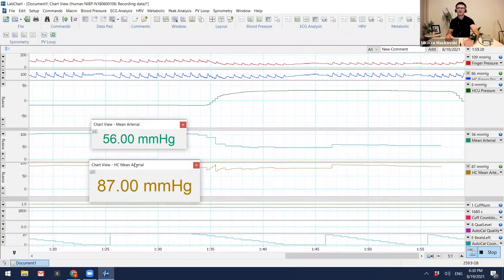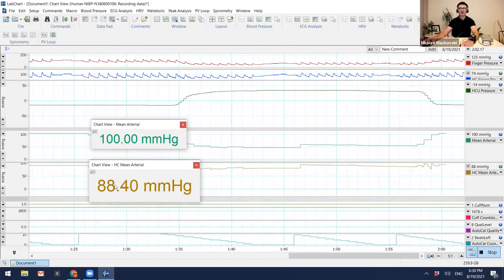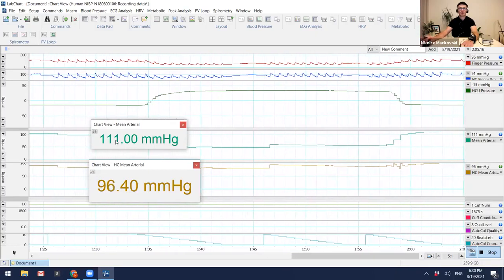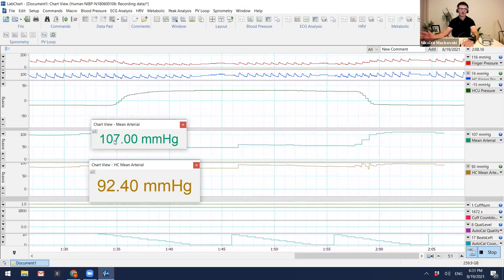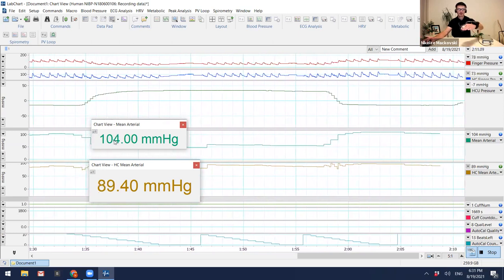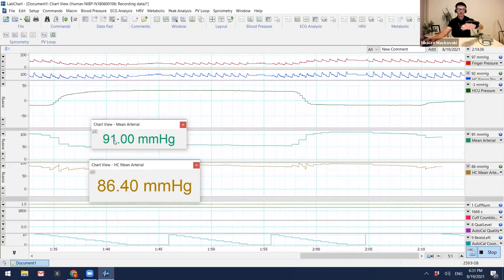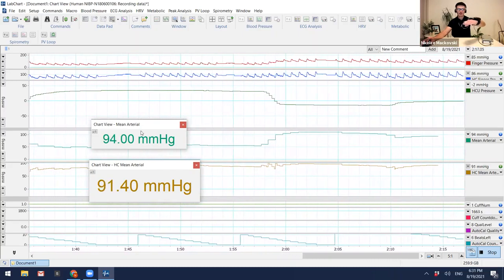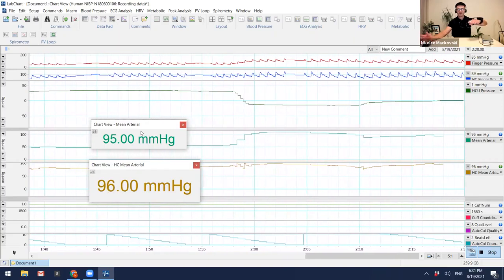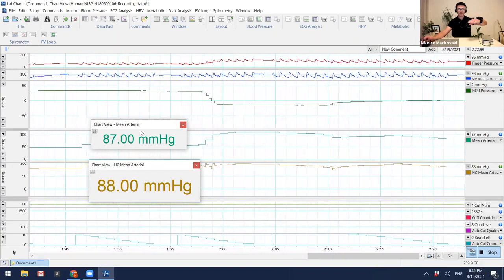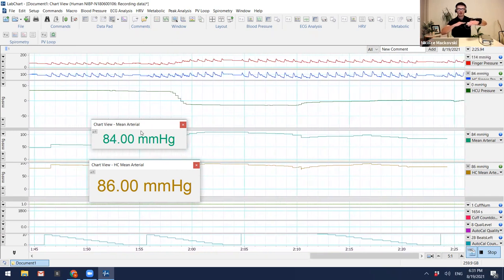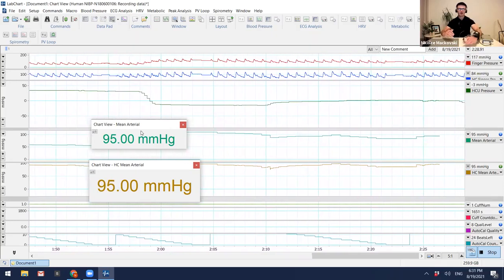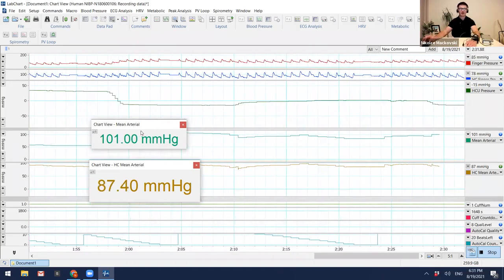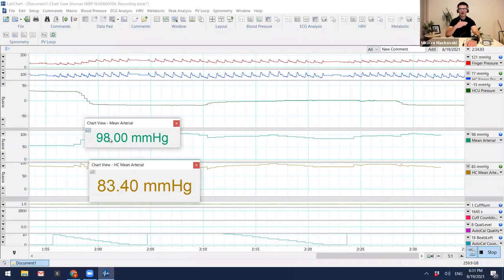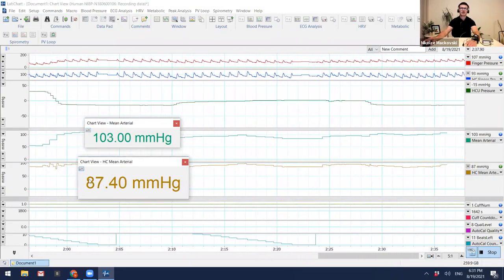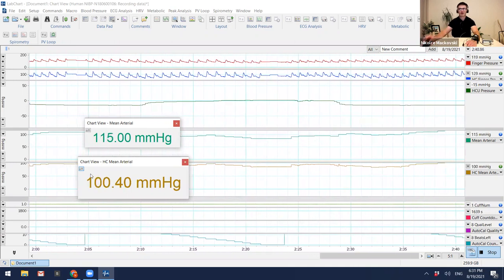And as we drop it back down, naturally this pretty much stays where it was, whereas this obviously goes back to a similar level. You can see there. So having them pretty much at the same level, that's at the same level as my heart right now. Therefore, we're getting a pretty good reading. That shows you the proof that right now that is the correct reading. Whereas when I drop my fingers lower than my heart level, then the pressure is a little higher than the actual heart level. So that's why the HCU is the one we want to be looking at primarily.